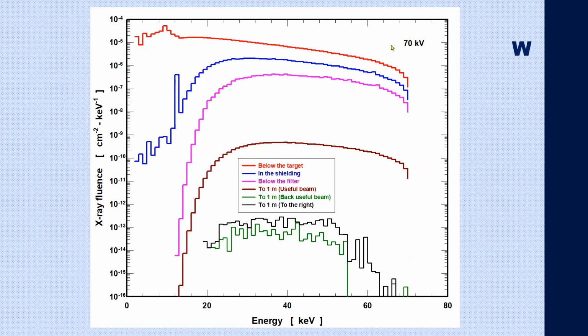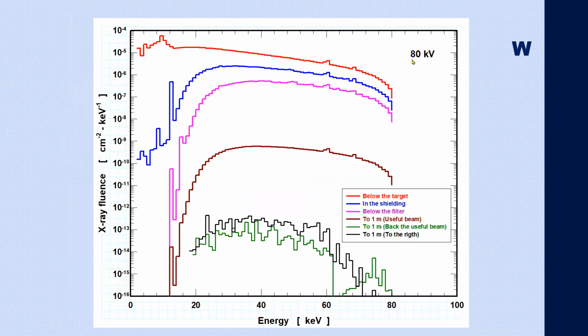Now I want to change to 80 kilovolts, but first let me point out that the endpoint of the spectrum is related with the voltage that we are using, 70,000 volts. When we change to 80, we barely notice the presence of the discrete contribution, the characteristic X-rays. We observe the same trend, the same tendency, as we move from the detector near the target to the detector allocated 1 meter along the useful beam. And also, we are including here the X-ray spectra of those photons that leak out from the shielding of the X-ray tube. We are going to change now to 90 kilovolts, and you will notice changes in the discrete peaks that become more relevant.